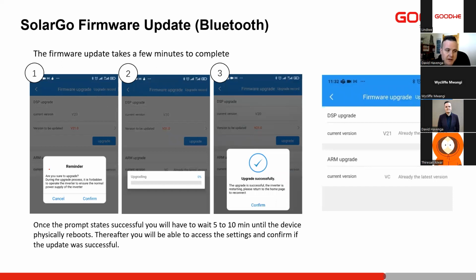You'll select upgrade, it will give you a reminder, and you'll see the upgrading bar will run. Once it reaches 100%, it will give you a notice and say, please note that the device is restarting, and you'll be redirected to the home page. So once this is 100%, you'll probably have to wait another 5 or 10 minutes for the inverter to do its reboot. Never restart the inverter, never switch the inverter off when doing a firmware update. Always leave it until it is finished.